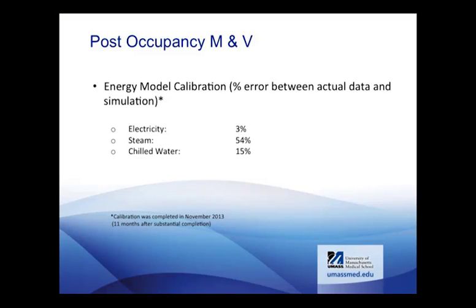The M&V effort was really not as rigorous as we had anticipated — more of a snapshot in time. The consultant came in, calibrated the model to the actual building, and gave us results. Those results were not encouraging. We took about 6 months of data, and the electricity was 3% high, which sounds pretty good — the threshold we were looking for was 5% — but this was while the building was partially occupied, so we're not really sure what that means at this point.